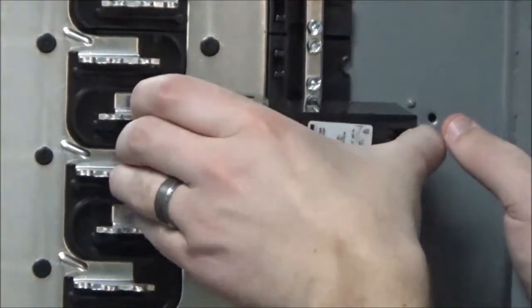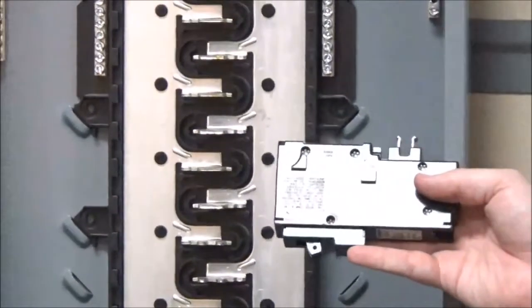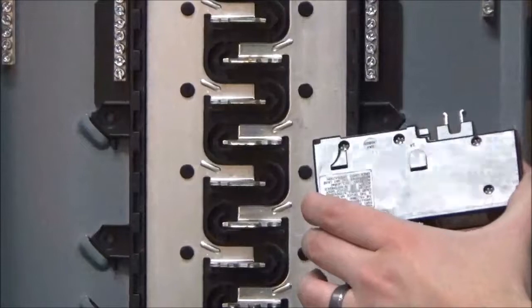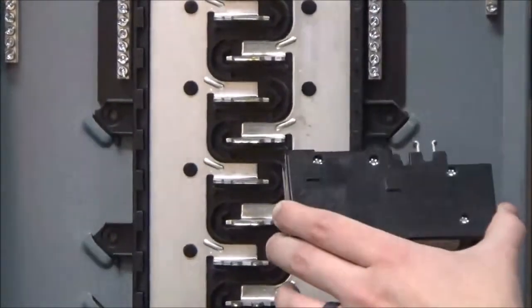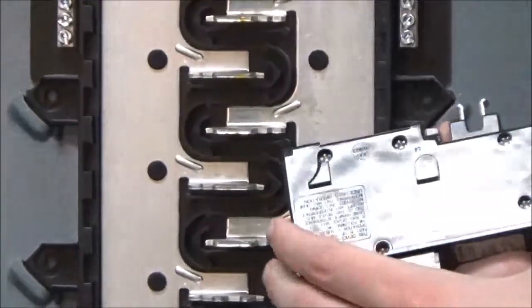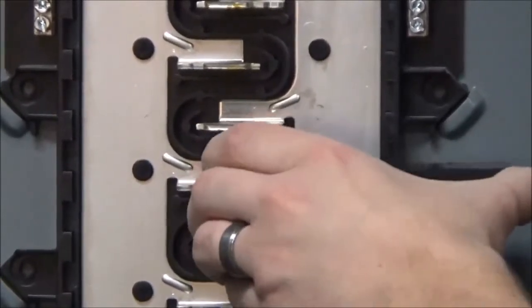You will see however if you try to install it in the old one that this clip has nothing to attach onto past the rail, and that this rejection feature is too thin to fit over the rail so that you cannot install it in a standard panel.